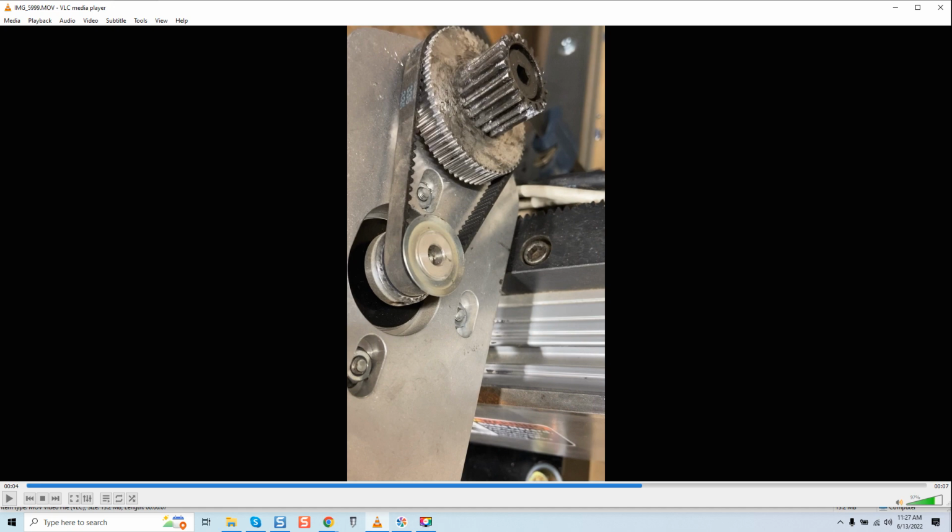We start breaking it down. Now, usually what ends up happening is that aha moment where you change a component and all of a sudden, like magic, the chassis becomes, or I should say the motor becomes normal in its rhythm. Everything seems right. We're moving again, no problems. Then what we want to do is isolate it even further. Is it the cable? Is it just the cable itself? Is it the connector? Is it just the connector itself? I mean, we got to go down the whole rabbit hole to see what is the part. And once we identify that specific component that needs to be replaced, we then replace it.